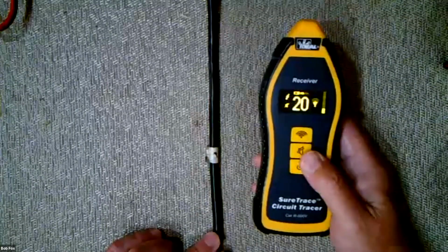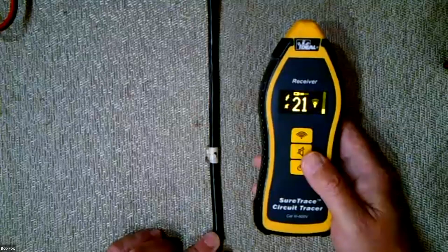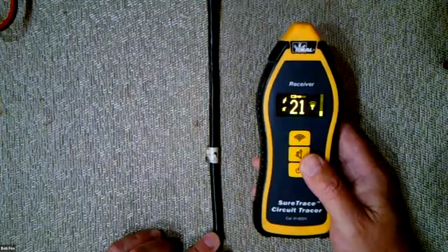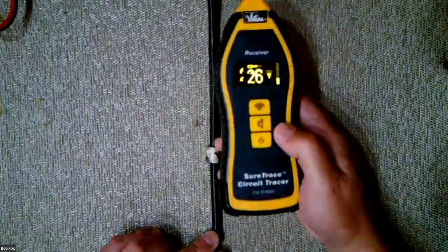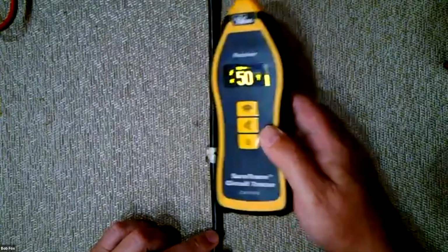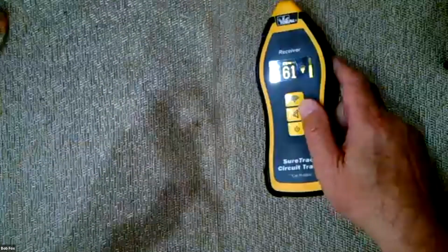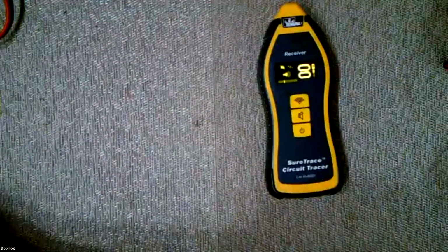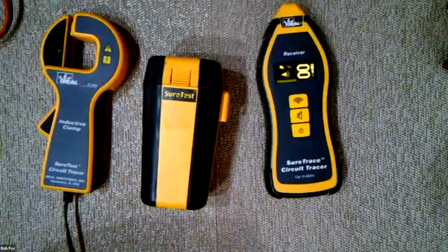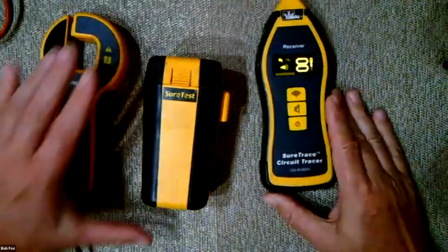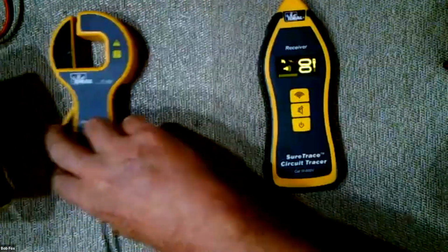Let's shut that sound off. I myself have located conductors that were in metal conduit under a few inches of concrete floor to within half an inch. So again, under the right conditions and under great conditions, it can be very, very powerful. So then next, what I wanted to show you was this guy. So I'm going to shut the transmitter off. So that signal should go away like you would expect. And of course it did. And additionally, we have this inductive clamp. I'll put the battery pack here.